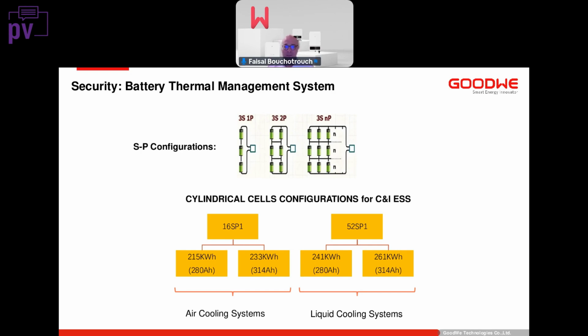This might answer one of the poll questions, whether it should be air-cooled, liquid-cooled, or hybrid. Air cooling uses air generated by fans to dissipate heat and maintain battery temperature. This system is relatively straightforward in design and doesn't require complex infrastructure, making it easy to maintain, which is why air cooling is much cheaper to install compared to liquid cooling.